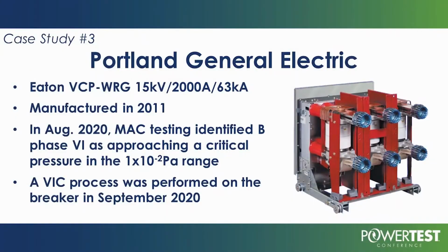The next project that we want to talk about is one for Portland General Electric, and we've done many of these. We could talk about them forever, so give me a call. This particular Portland GE breaker was a VCPW breaker. We're not trying to hit any one manufacturer; we're talking about ABB, GE, Eaton Cutler-Hammer. There's really no distinct advantage between them from our perspective, and that's why we've broken it out this way.